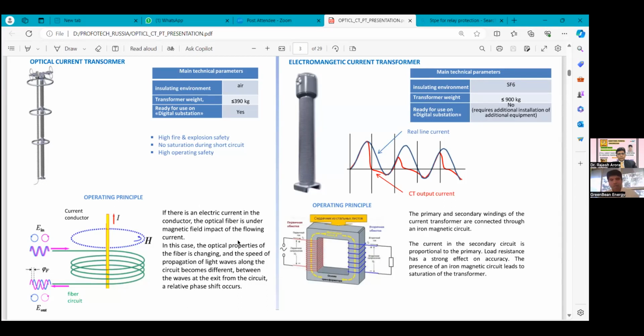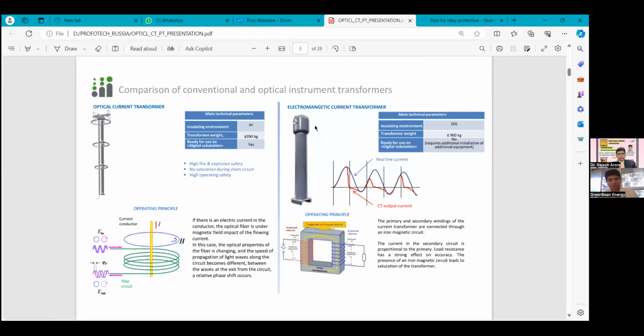Here the mechanical difference is, if you see the electromagnetic current transformer, it is filled with SF6 or oil. The transformer weight is around 900 kg, and it uses core and copper for manufacturing, and oil. But in the case of the optical current transformer, the weight is less than or equal to 390 kg, and there is no oil, no copper, no core material used for manufacturing this optical current transformer. Apart from this, there is no fire hazard or explosion possibility. Compared to a CT, there are chances of fire and explosion hazard.